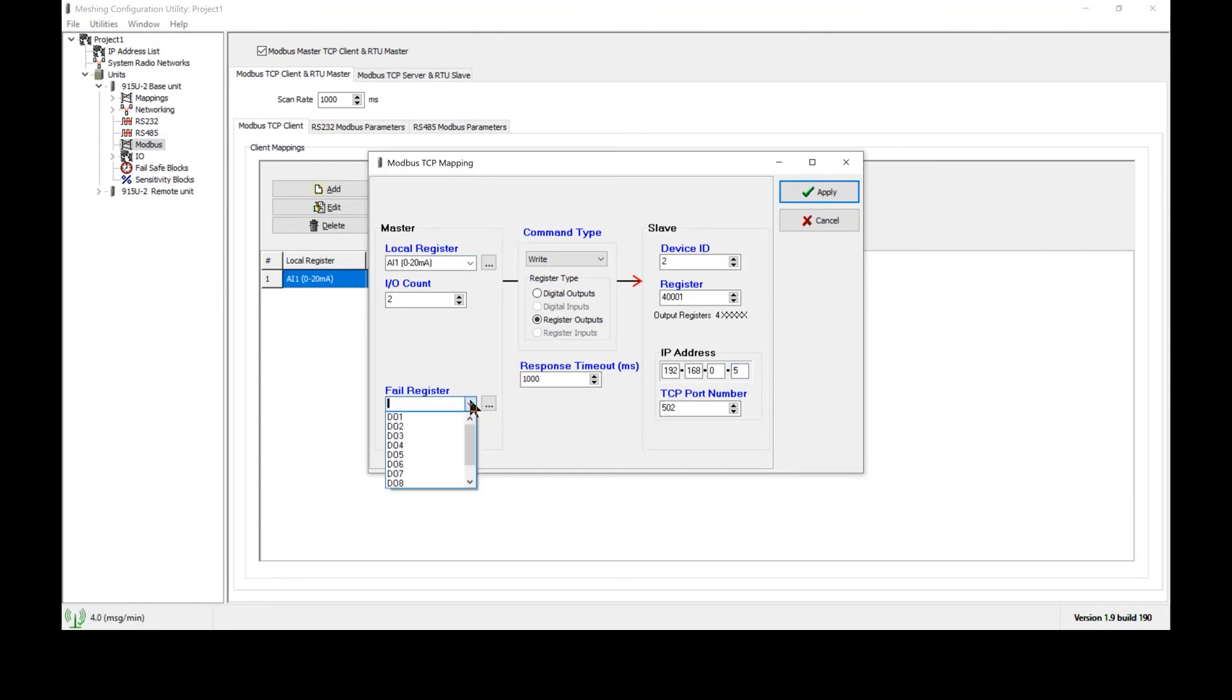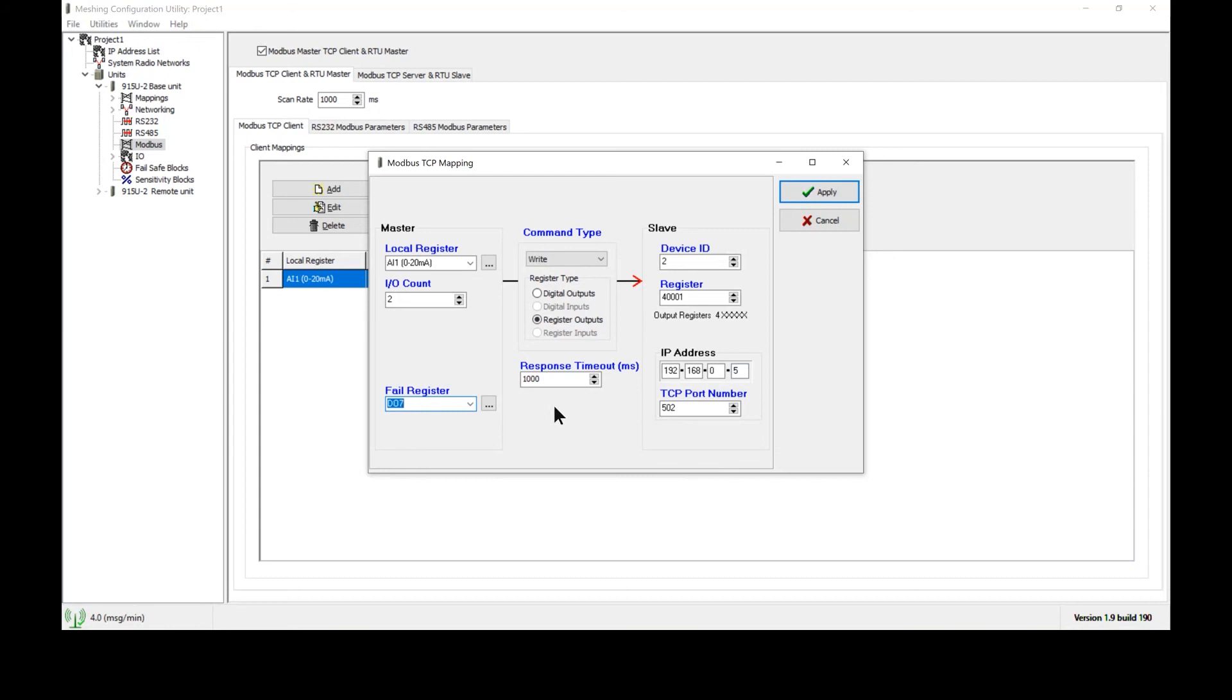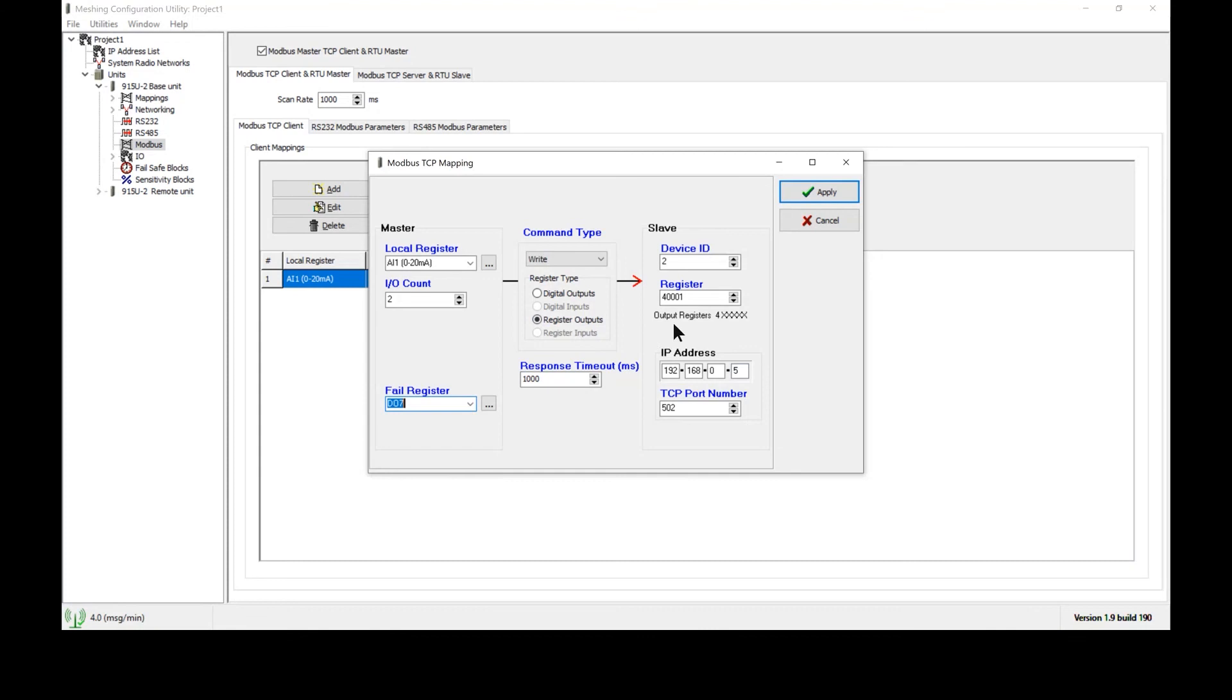Lastly we are going to create a fail register and in this case I'm going to pick digital output number 7. There is an LED on the terminal block next to digital output 7 which shows the status of this register. By observing the LED you can visually tell whether this mapping was successful. When the radio sends out a mapping to the PLC and the PLC responds to that mapping, that acknowledgement is used to determine the status of the fail register. If the transmission failed or if no reply was received, then this LED will turn on and digital output 7 will become active. When DO7 is off and the LED next to it is also off, then communications were successful between the 915U2 and the PLC.